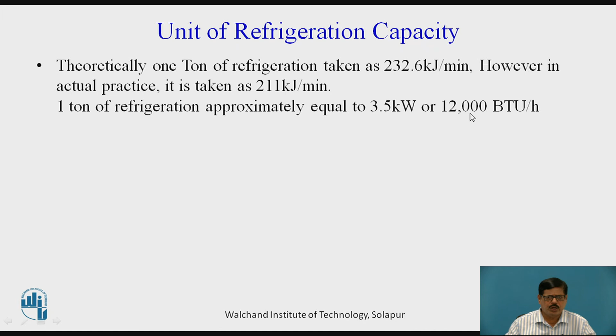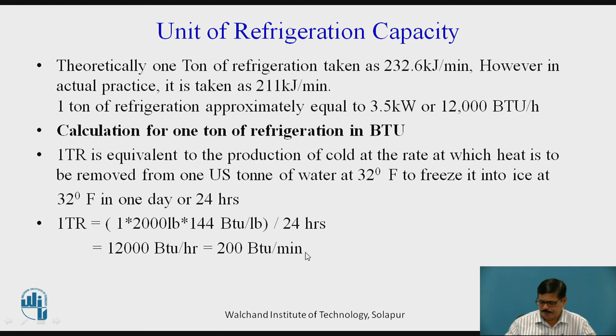Now, let us see how to calculate 1 ton of refrigeration in BTU. So, 1 ton is equivalent to production of cold at the rate at which heat is to be removed from 1 US ton of water at 32 degrees Fahrenheit to freeze it into ice at 32 degrees Fahrenheit in 1 day or 24 hours. We know that 1 ton in the US is equal to 2000 pounds. So, 2000 pounds into the latent heat of fusion, which is 144 BTU per lb, in 24 hours. So, divide by 24 hours. It comes out to be 12,000 BTU per hour, which will be equal to, if you divide by 60, 200 BTU per minute.